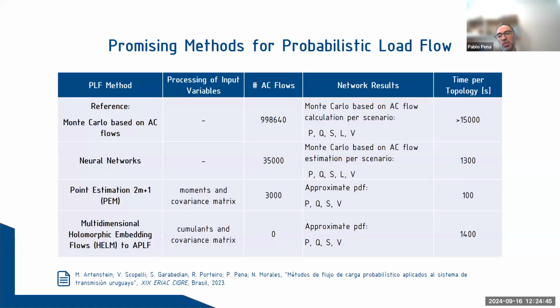The point estimation method uses any traditional load flow solver. We in Uruguay use the PSSE of Siemens. And the idea is to solve a kind of scenario by combining different input moments. It requires solving only, for the case of Uruguay, only 3,000 AC power flows.